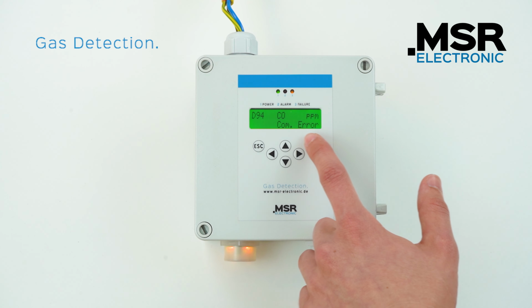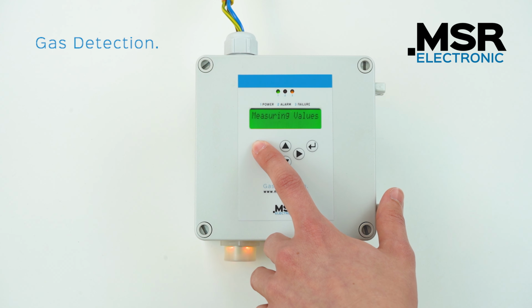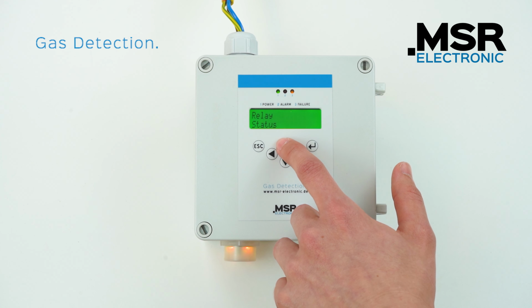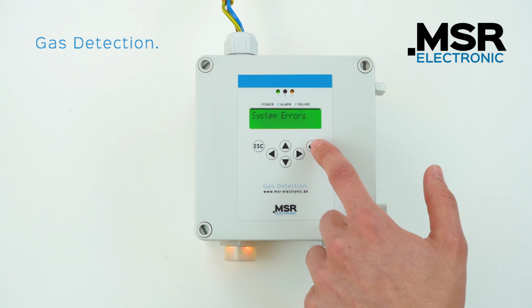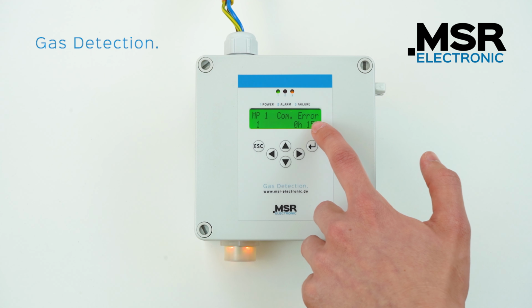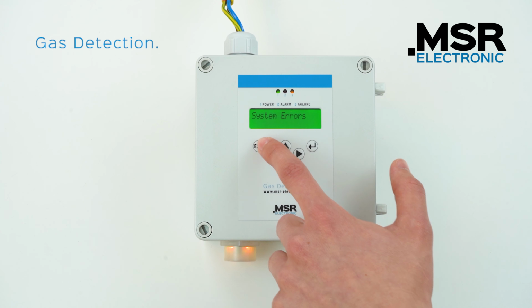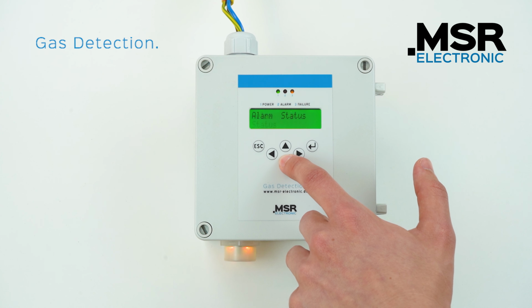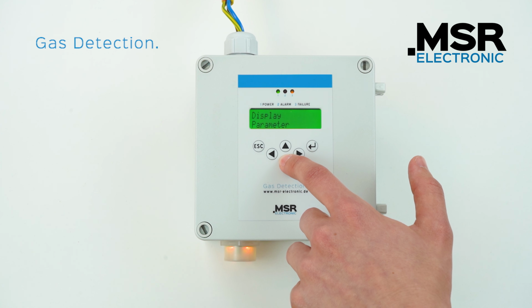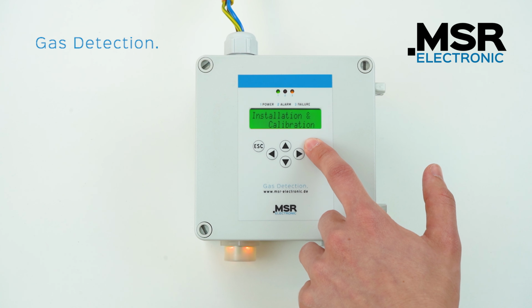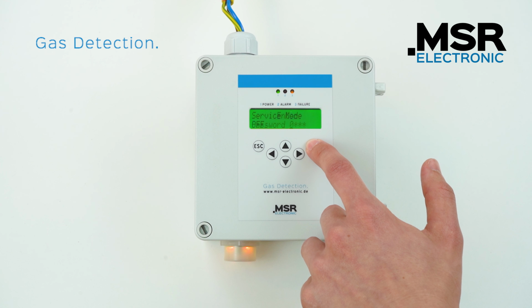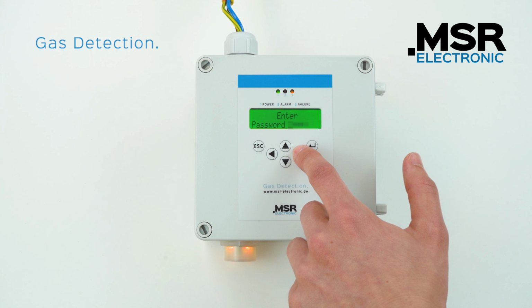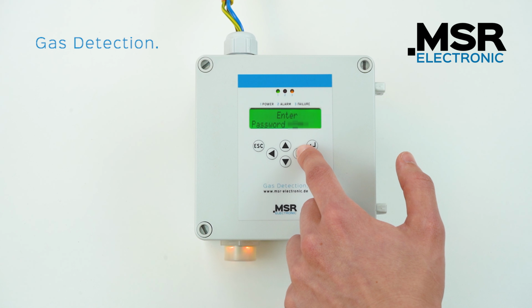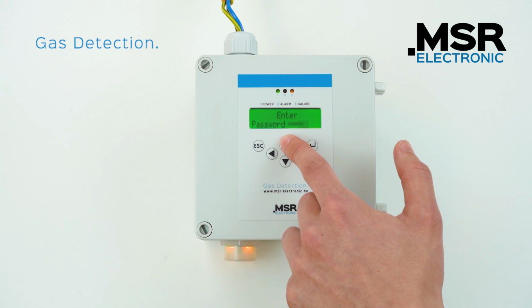The communication error is indicated by being displayed on the display instead of the measured value and can also be seen in the error status. Please carry out the following steps so that you can rectify the error. To begin, navigate to the parameters and activate the service mode. To do this, enter your 4-digit password.